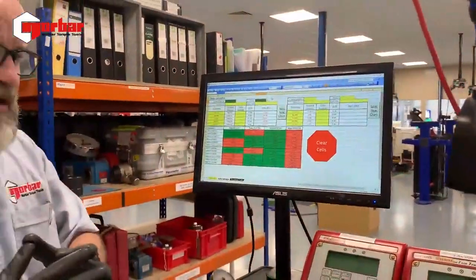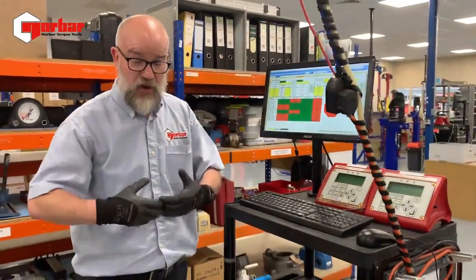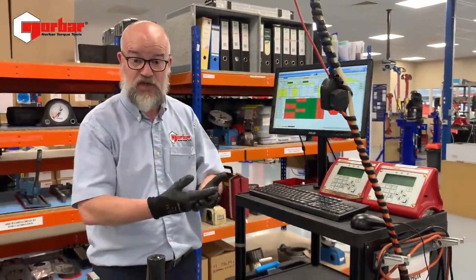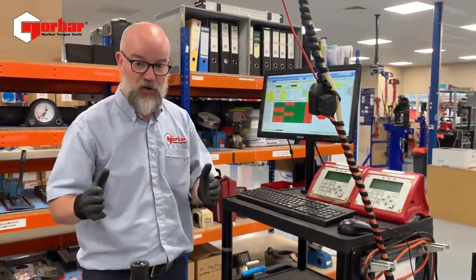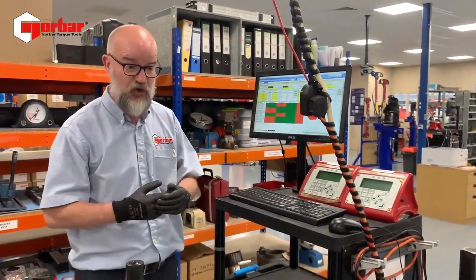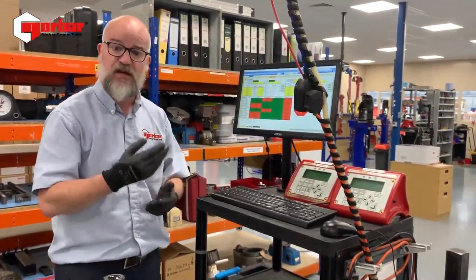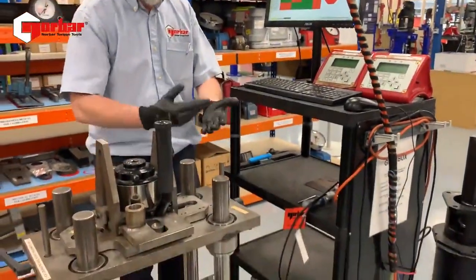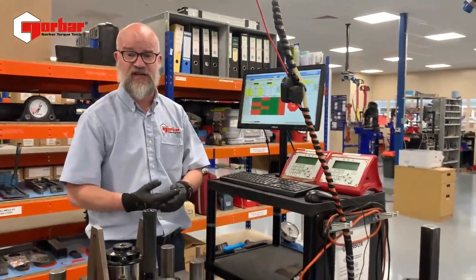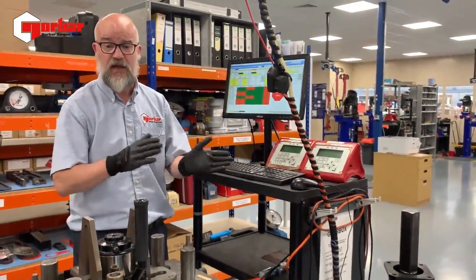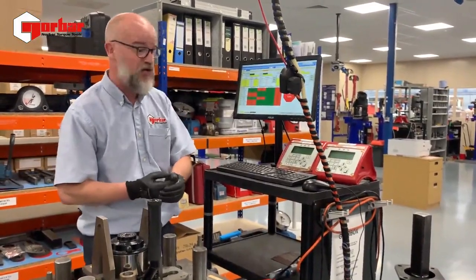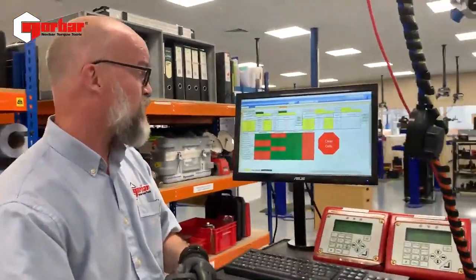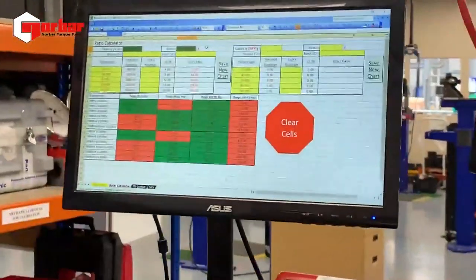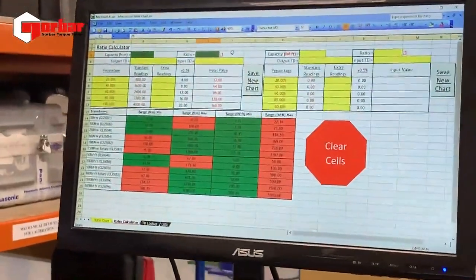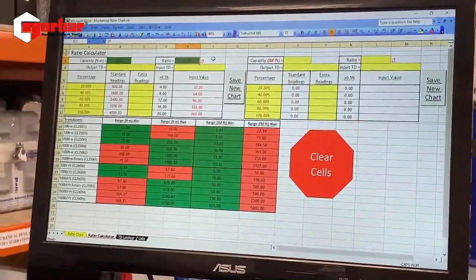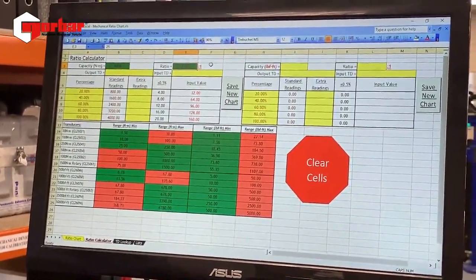In our laboratory we would collect data on a worksheet and it goes into our bespoke software, which is developed for our laboratory. You may well wish to work on an Excel sheet where you're taking the transducer torque output against the torque input, factoring in your uncertainties to give you those ratios. Again, guidance notes and methods are contained within the manual, but I'm going to show you the system based on what Norbar are doing. So I've got my outputs, which are 800, 1600 Newton meters, 2400, 3200, and at full scale 4000. And against my inputs.